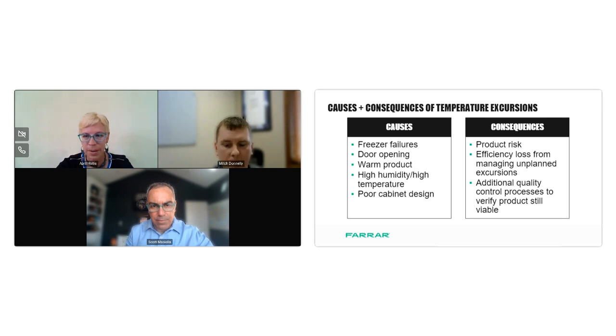All right, Scott, would you add anything? You know, the one thing that I would add is that as you're pulling material down, you're adding a tremendous amount of heat into the space. And when you open the door, same thing. The air that's inside of that freezer can be upwards of 100 degrees Celsius different on the inside than the outside. When that happens, the air is very heavy and falls out of the freezer. You don't often see that in the chest, hence that configuration, but you still have recovery issues at any upright. And so being able to recondition that space again after opening the door or inserting warm product is the biggest challenge of any cold storage equipment.